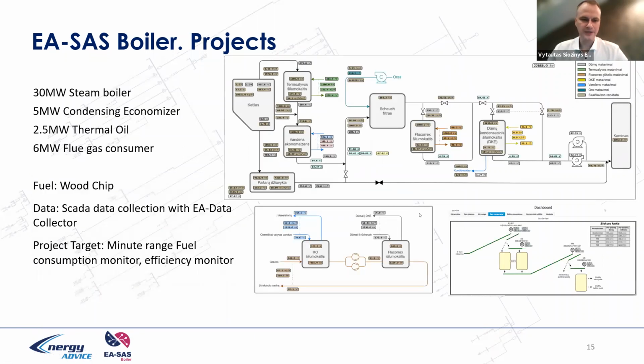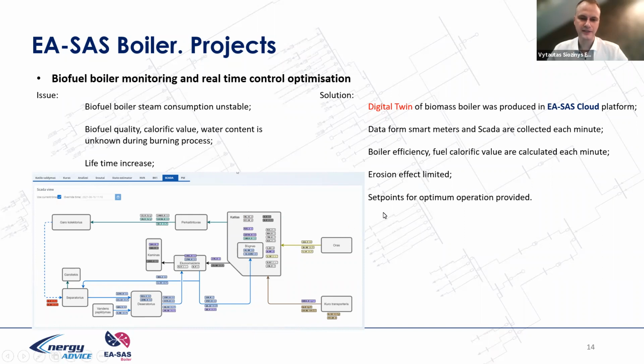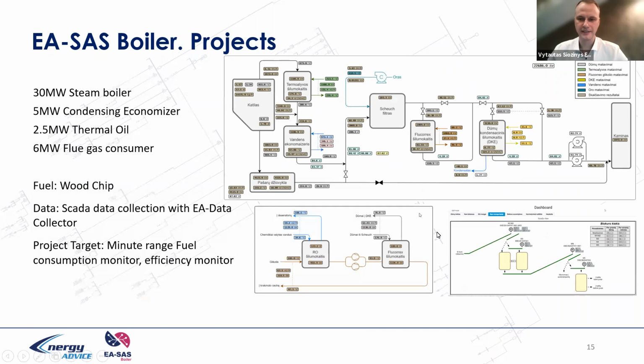Next example, more comprehensive: this boiler has 20 megawatt steam output, and this one is 30 megawatt, with a 5 megawatt condensing economizer, 2.5 megawatt thermal oil heat consumer, and 6 megawatt flue gas consumer. On this wood chip boiler, we install data collector software as in the previous project and collect all data from the SCADA control system, and visualize it in the same EA-SAS cloud dashboard. And the project target was to monitor fuel consumption.